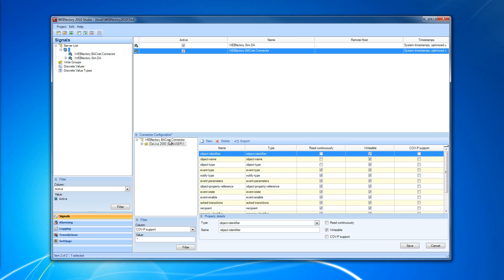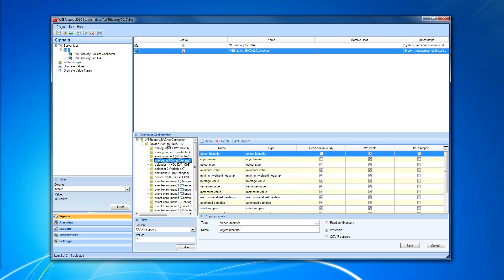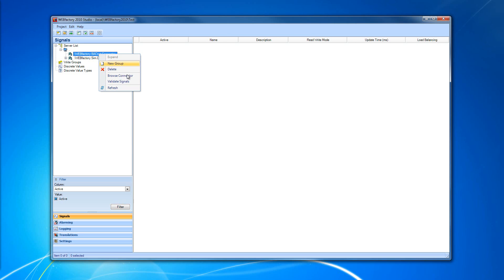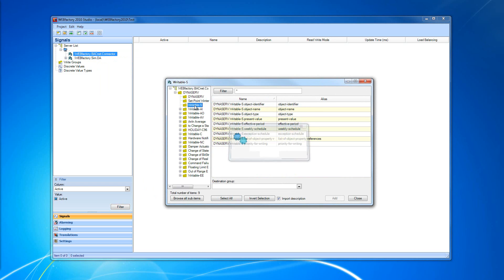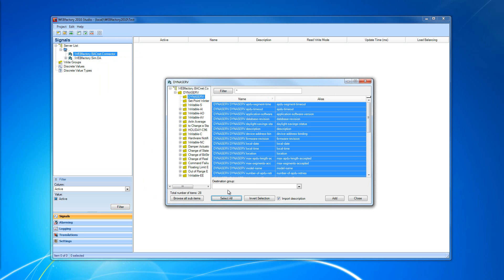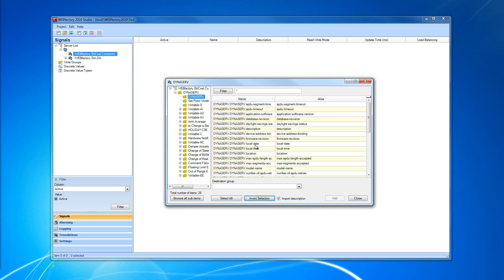The whole purpose of using the BACnet connector in WebFactory Studio is being able to add signals from the BACnet connector. Once we have our BACnet device loaded into our connector, we're going to save the configuration, then right-click on the connector and select Browse Connector. In the Browse Connector window, we can see each of our BACnet devices has a list of properties that we can select to import.